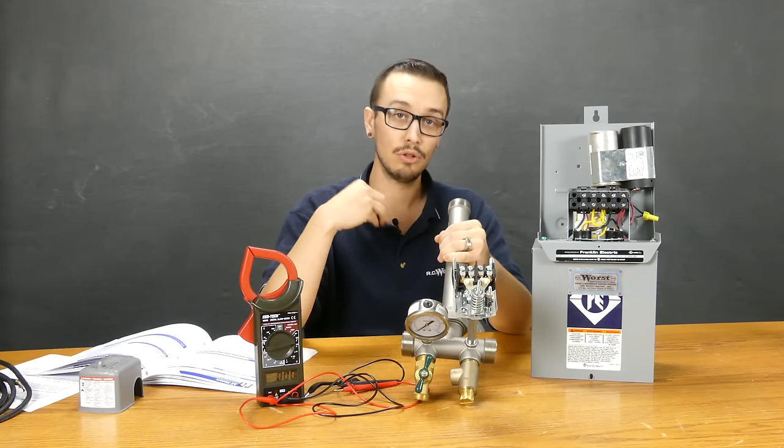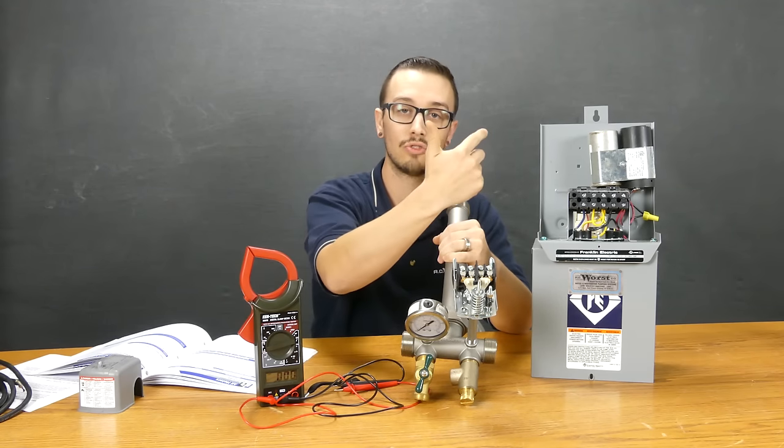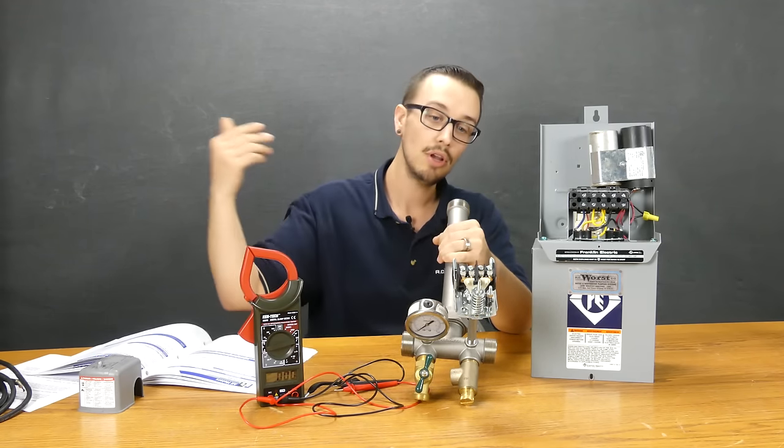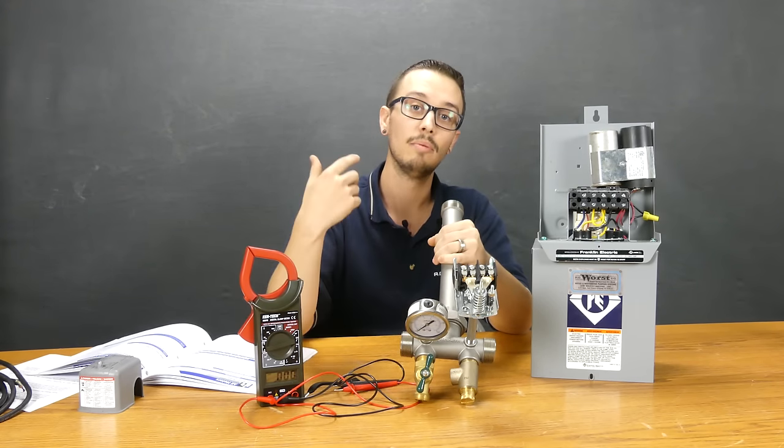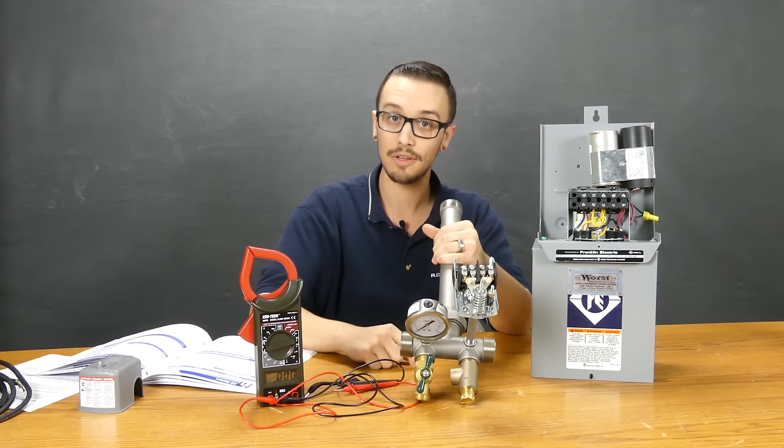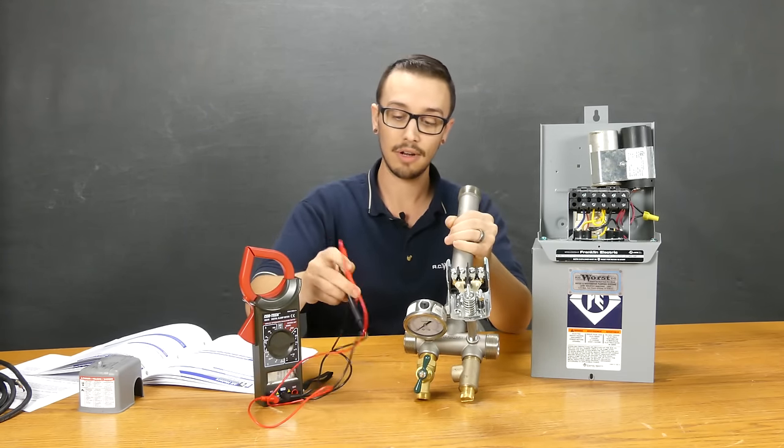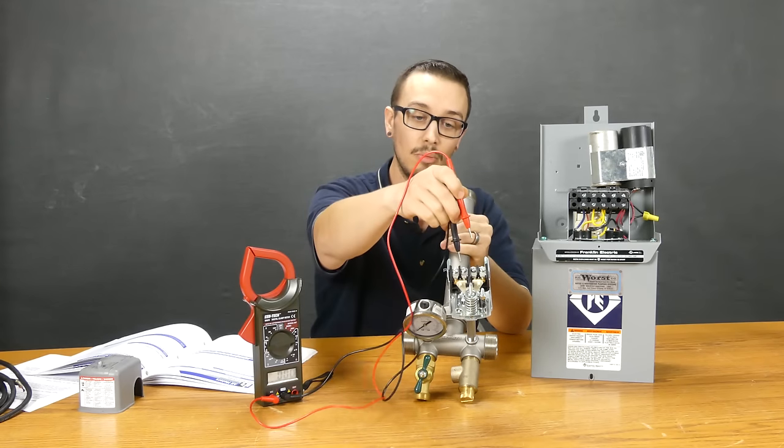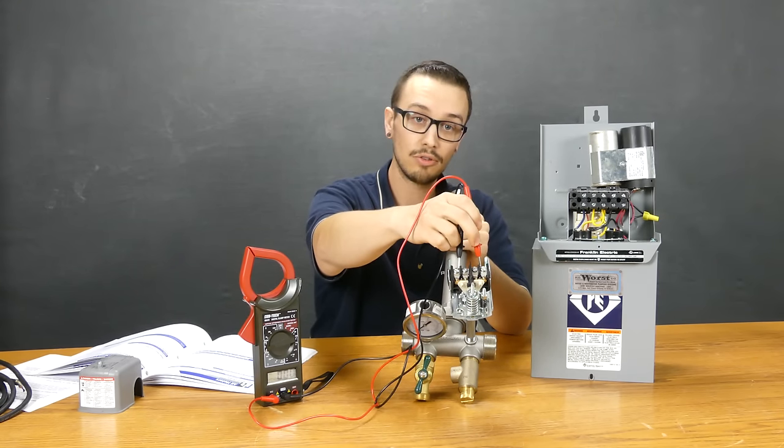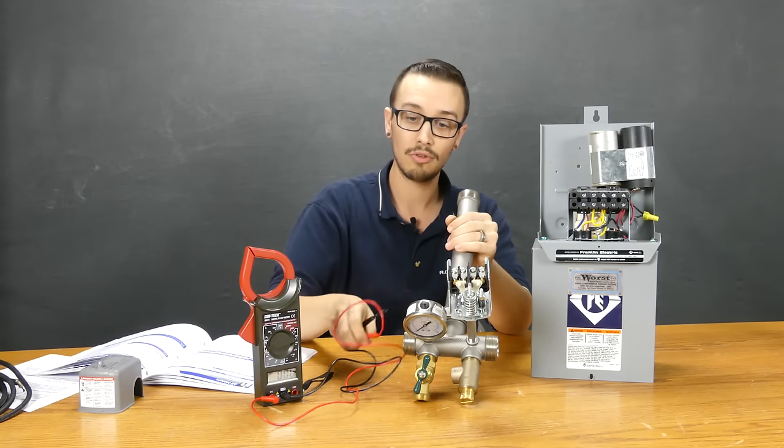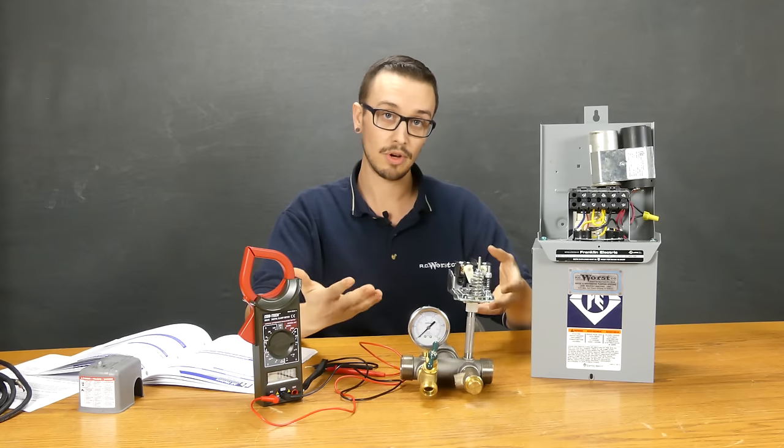Check the load side voltage. The load side would be the wires running to the control box, rather than the wires running to the pressure switch. This will allow you to confirm that power is getting through the pressure switch and making its way into the control box. Put the meter leads on the appropriate screws leading to the control box, and you should be reading 230 volts or plus or minus 10% to confirm it's working properly.